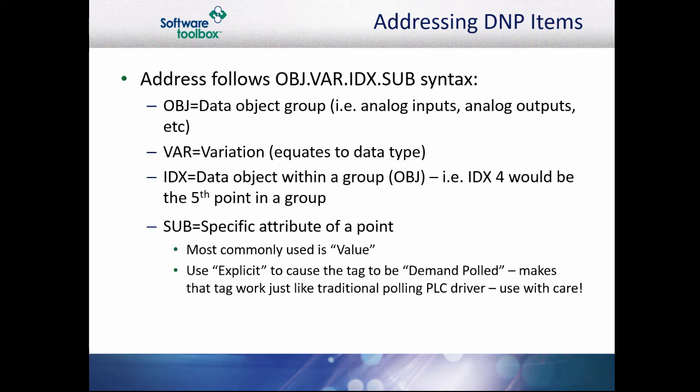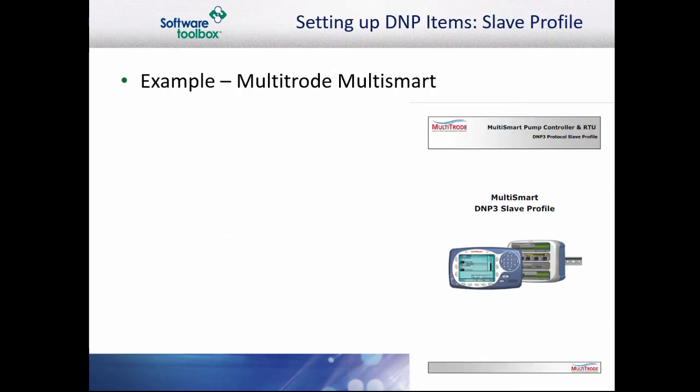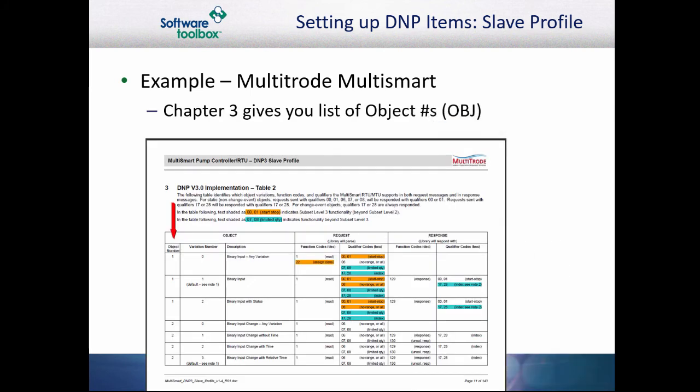When setting up DNP3 tags, it is essential to have the DNP3 slave profile document for your device. This will let you know what the DNP3 addresses are used for, what event class they belong to, and how to access them. Here is an example of a slave profile from a Multitrode MultiSmart pump controller. Chapter 3 lists the object numbers, the various available variations, and their descriptions.